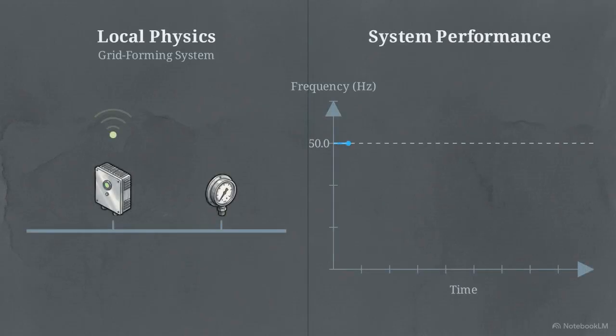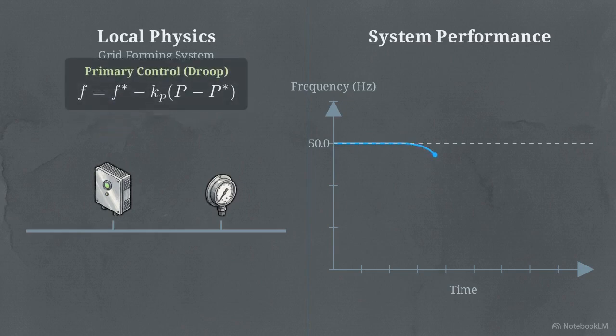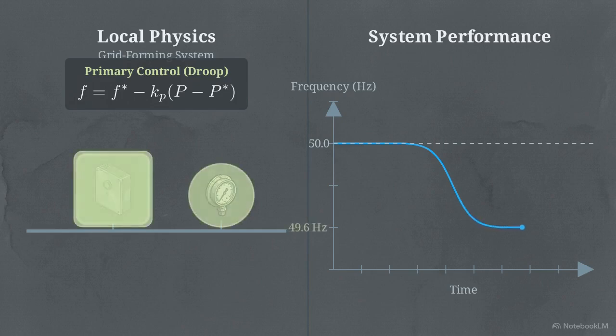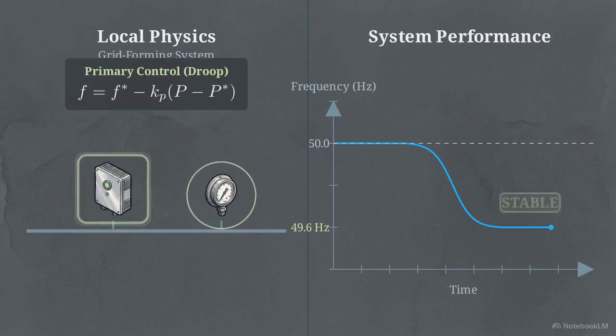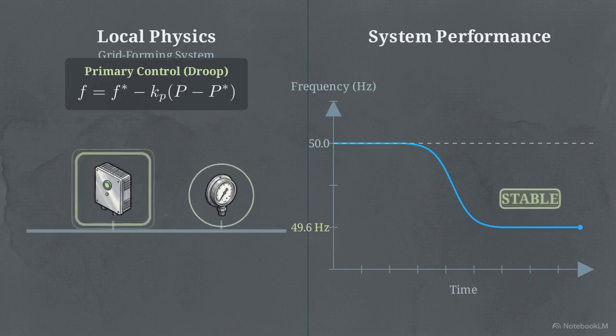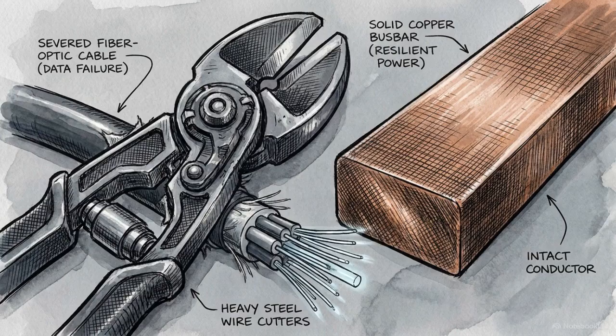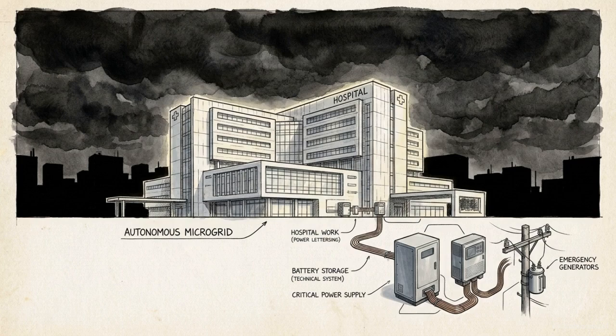The grid-forming inverters rely purely on terminal physics. Their droop control logic requires zero external data to function. The grid does not black out. It remains stable, though the frequency will safely settle slightly off nominal, around 49.6 Hz. By mastering inverter physics, the math of energy storage, and the boundaries of data reliance, engineers build a system capable of sustaining vital power even when the centralized grid is lost.